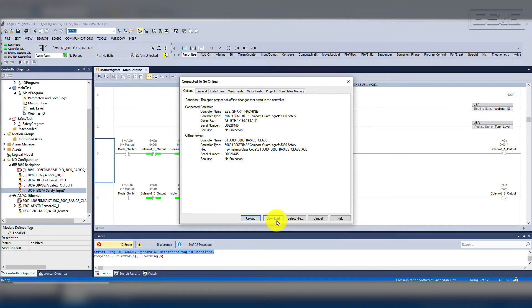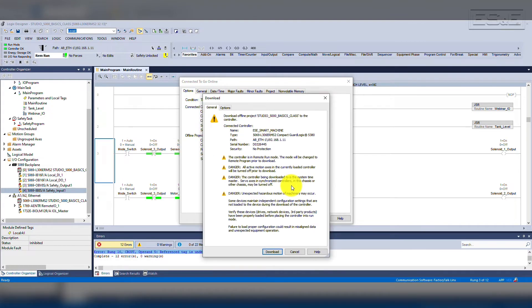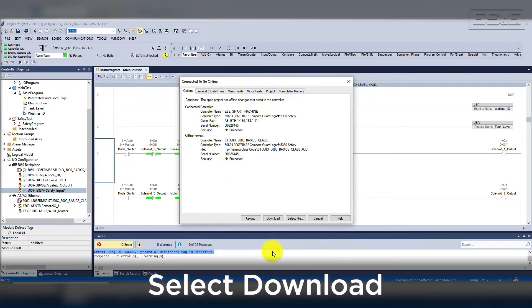Starting with version 21 of Studio 5000, the comments, descriptions, and tag names were all stored in the controller, so you do not lose any data by selecting Upload. When downloading, you should ensure that you have the proper project and controller connection. Once you hit the Download button, the software will pop up another window confirming that you will be downloading, which will break all other communications with the controller and overwrite its memory. Select Download again.